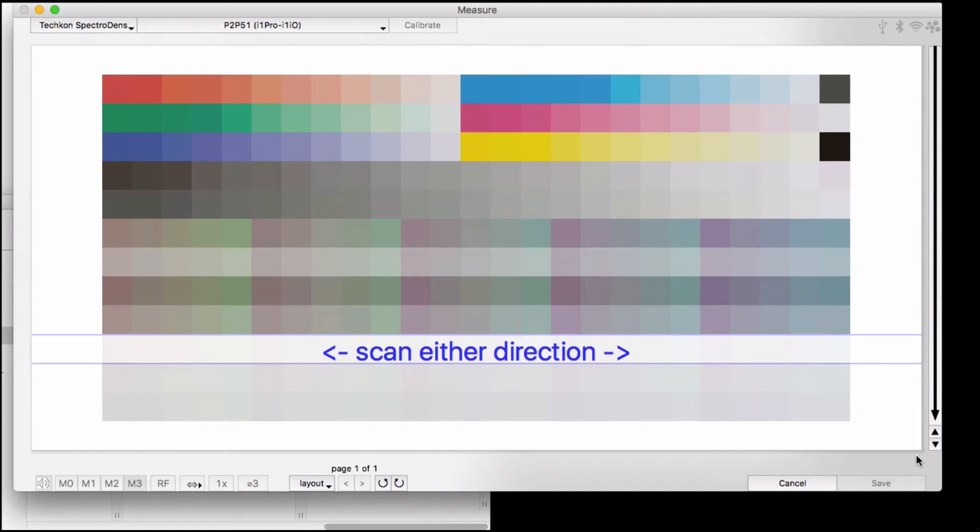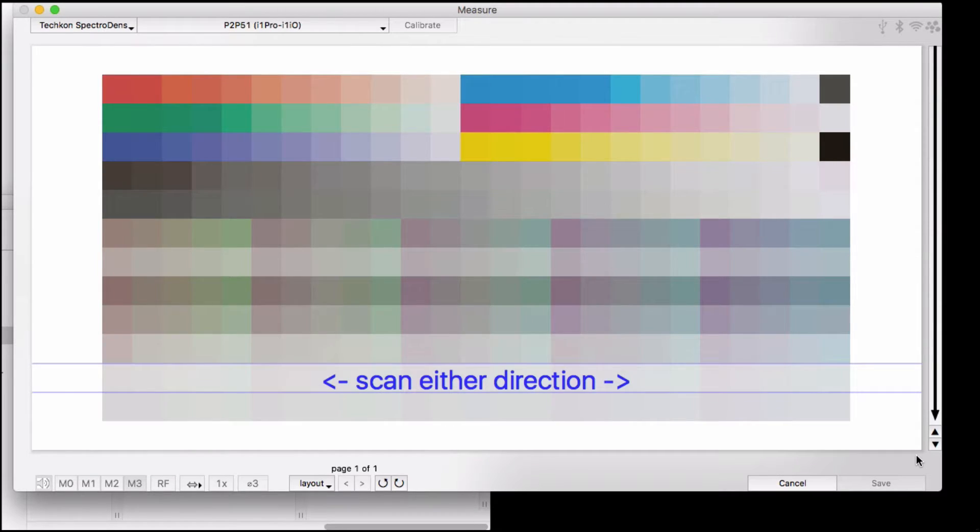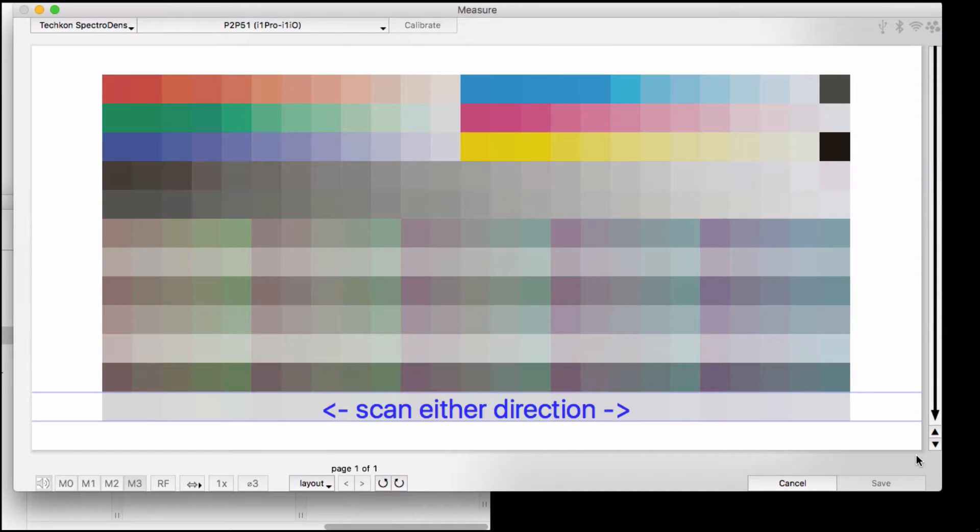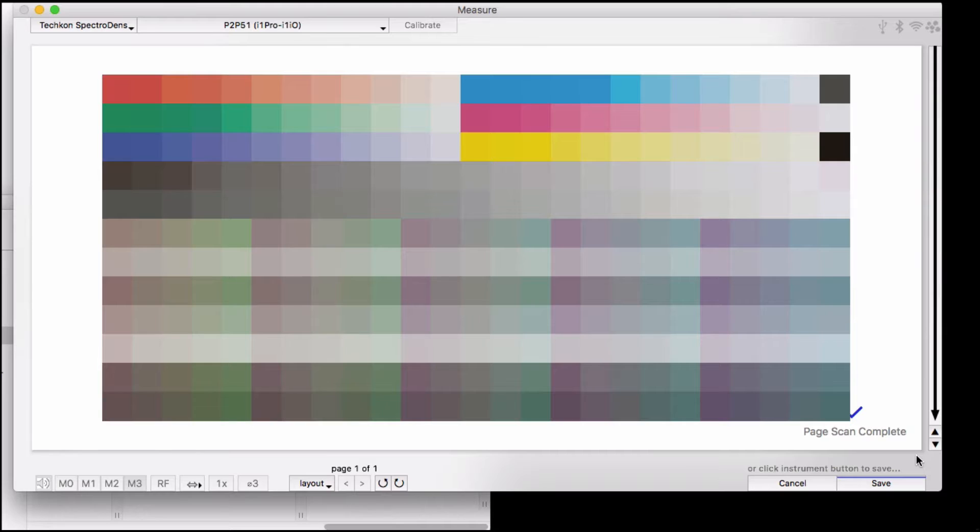You do have the option of measuring in strip mode or one-by-one in spot mode. You could even measure the whole target one spot measurement at a time if you wanted to. When you're done, click the green measurement button again to save the measurement, or click Save in the software here.